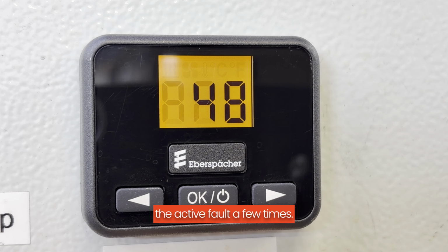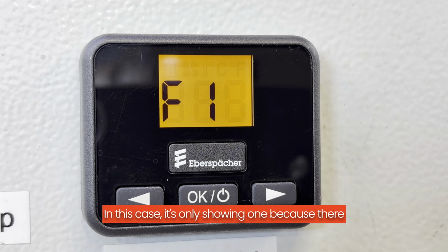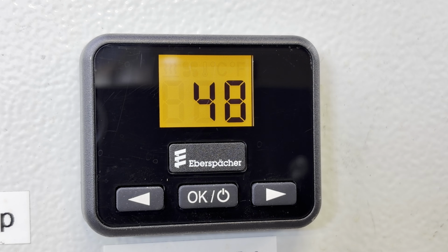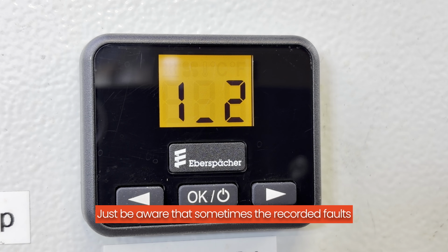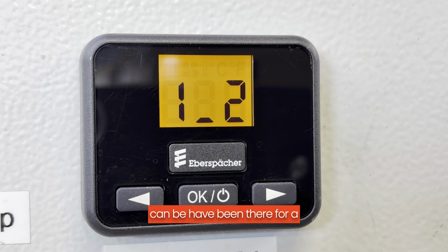The next thing you can do is press the right hand button, and that takes you into 12. 12 will then cycle through all faults that are stored in the heater. There can be up to 6 of them. In this case it's only showing 1 because there is only 1 recorded fault. Just be aware that sometimes the recorded faults have been there for a long time or can be quite old.